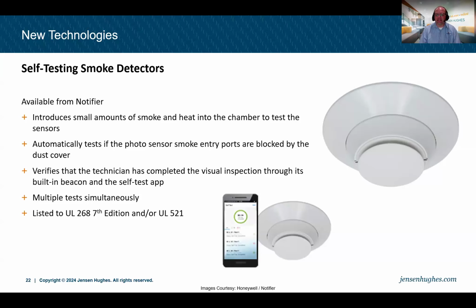You can do multiple tests simultaneously, and it's all to the latest editions of those UL 268 codes that I was referring to earlier. So really, really neat technology, which could be really, really beneficial in some occupancies and really cut down on the distraction for the annual testing of smoke detectors.